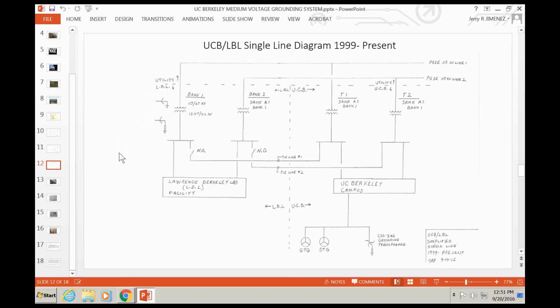The reason I asked is I just want to make sure I understand. So with the high resistance grounding, with the low resistance grounding, with the neutral grounding resistance that you have, it's only got a 10-second rating. So basically, you must clear that fault. So you're still in a situation where you must trip, just like you would be in a solidly grounded system.